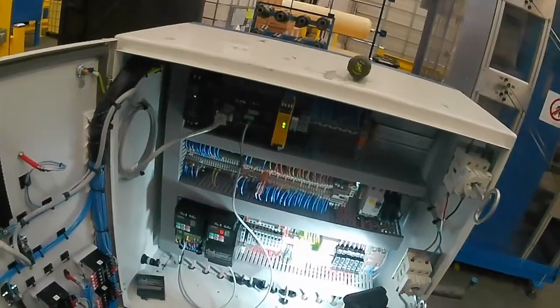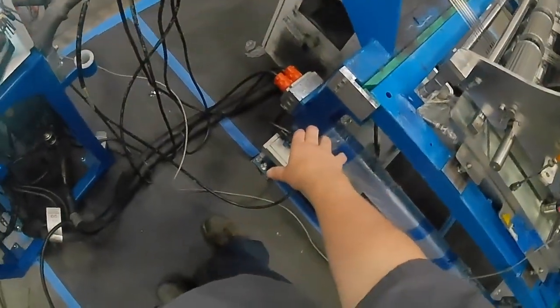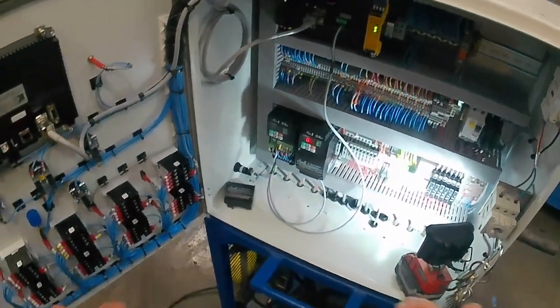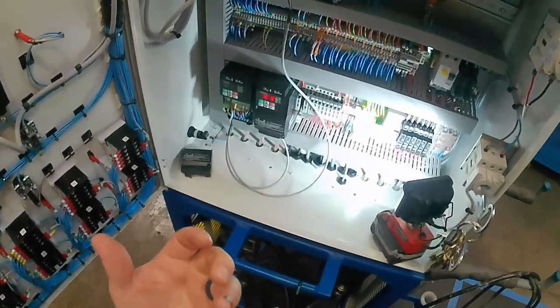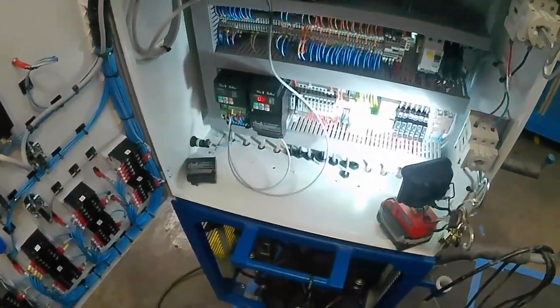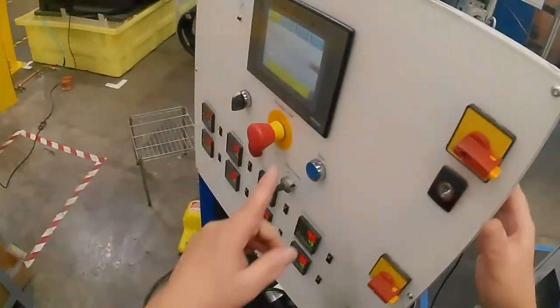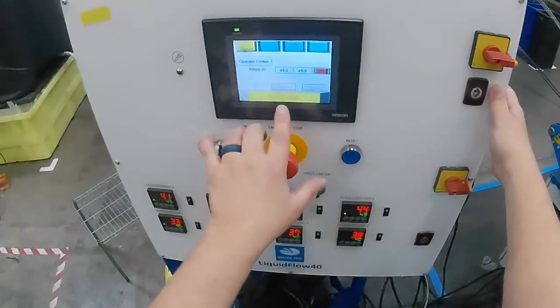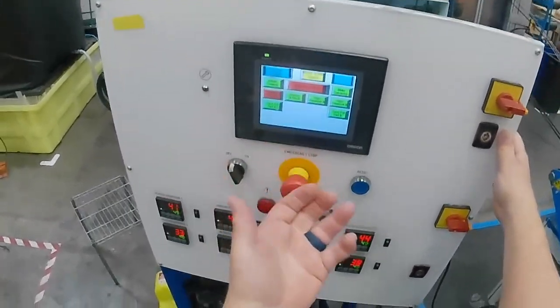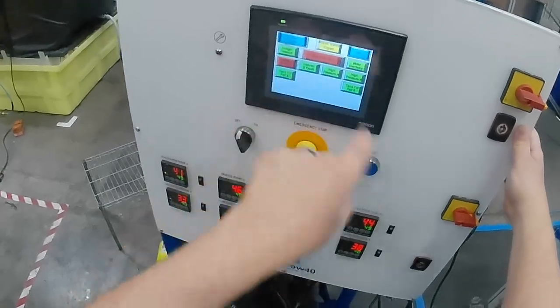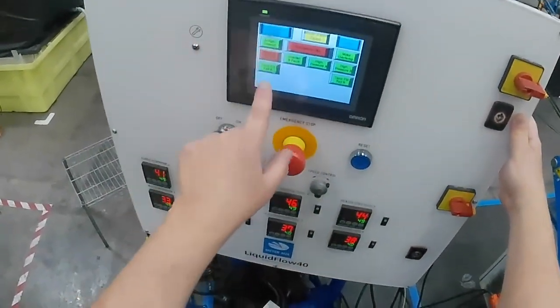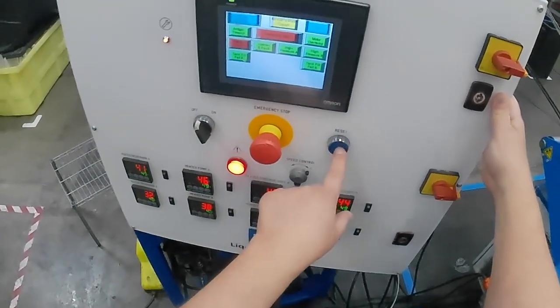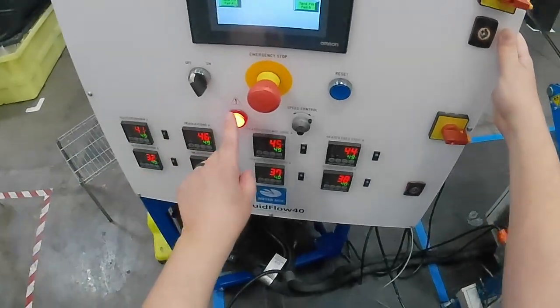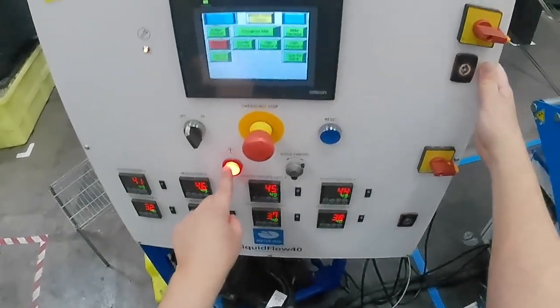Okay, so we have power. Originally we had no power to the outlet, which could have been caused by the fuse, I don't know. Now on the second part of this, we did some troubleshooting. We noticed that after we powered everything up, we had a fault on our HMI screen, and as soon as you hit to call for what the fault would be, it's saying inverter A fault, which is highlighted in red, which is a big issue. You know you're in fault condition because your fault condition lamp is illuminated.